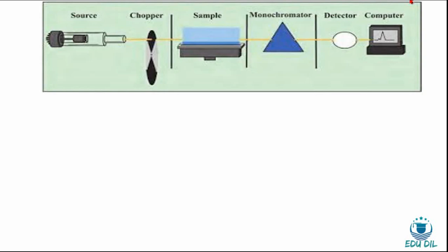Then you have the sample, and the sample is placed in this way. The nebulizer sucks the sample solution into the flame, and the flame forms gaseous atoms, and your beam of photons passes through these atoms, and after some absorption the remaining beam comes out. This goes through a monochromator. The monochromator lets the beam separate into different wavelengths.